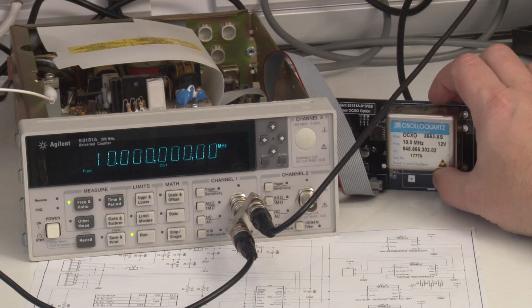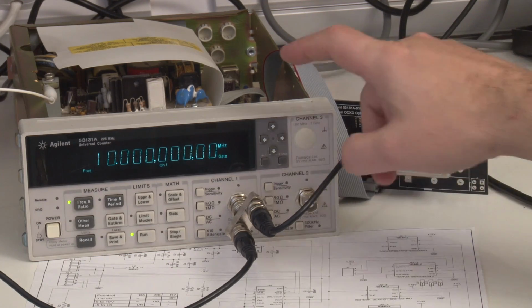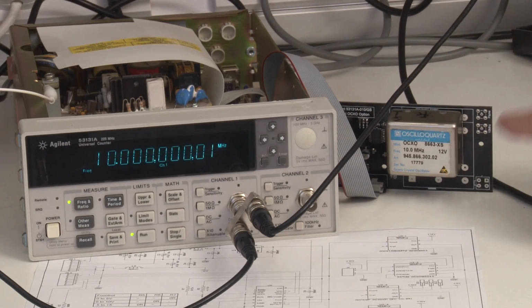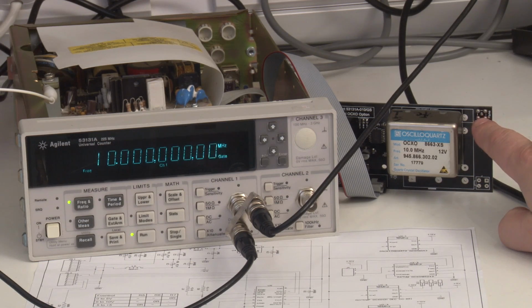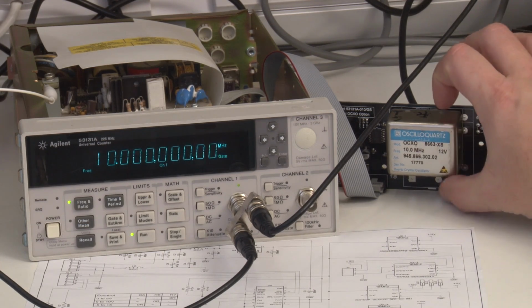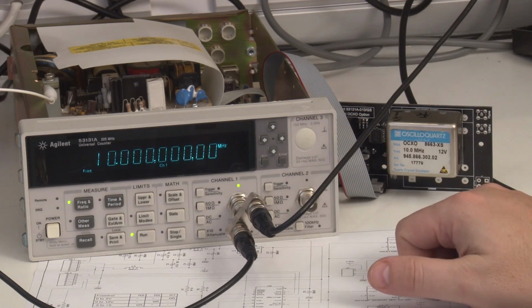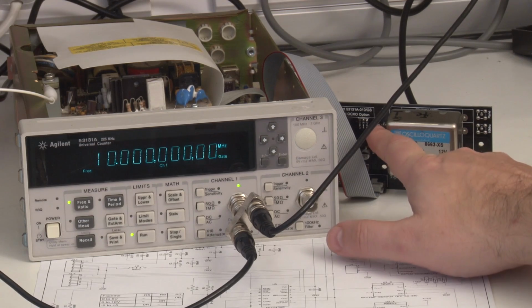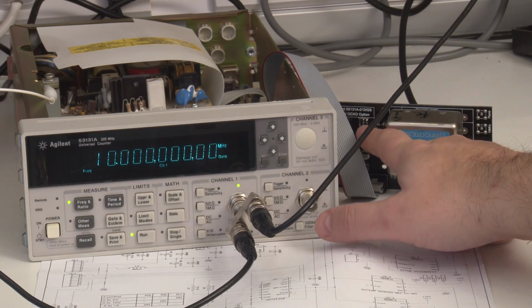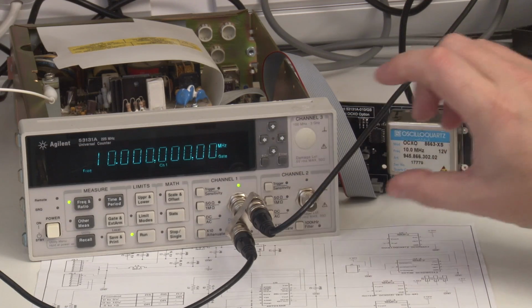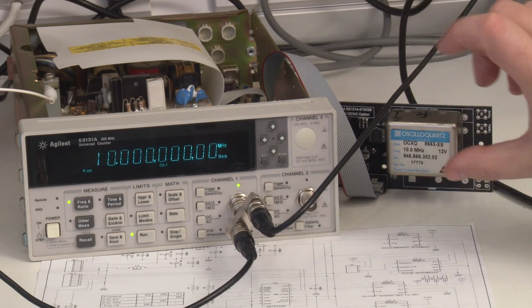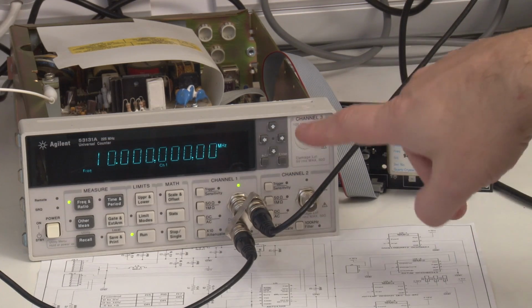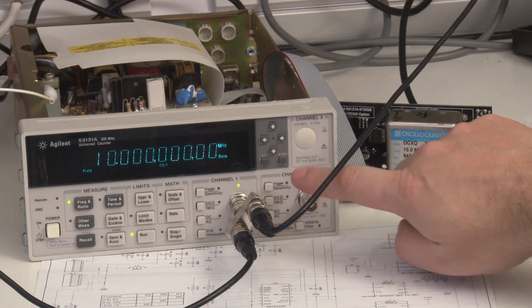Now this OCXO is rated at 0 to 10 volts, and watching it try to calibrate, it was actually failing the calibration on this oscillator. Measuring the frequency control voltage, what I found was the calibration routine would only pull it down to 5 volts. It wouldn't go any lower than 5 volts. So it couldn't, and therefore it was failing the calibration each time. So just to prove a point, I moved over to the 0 to 5 volt range, just to see if it would pull it into range, which of course it has done. It's calibrated it now, and you can see it's done a pretty good job.